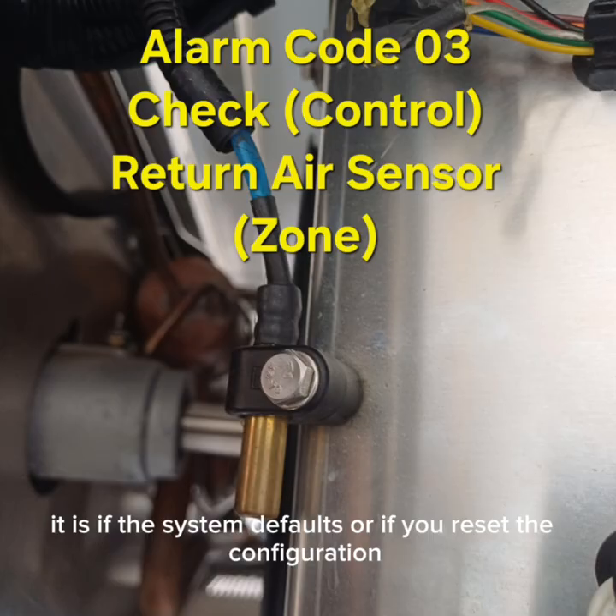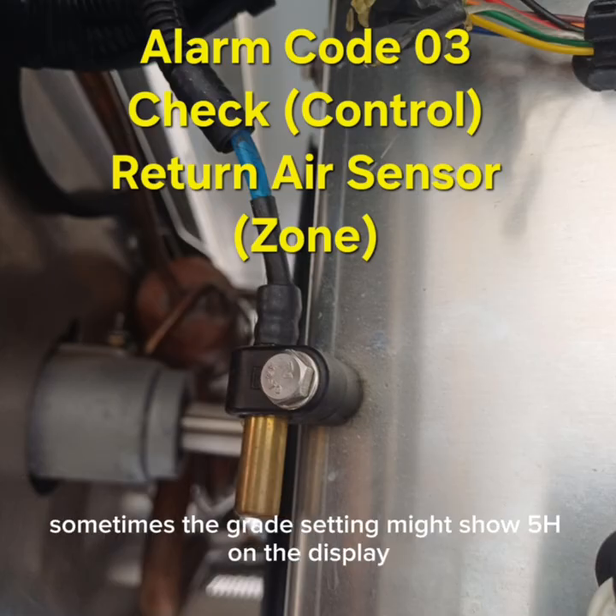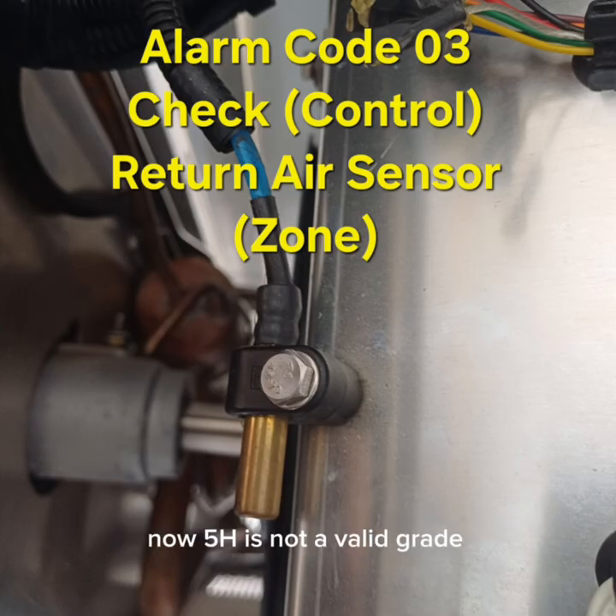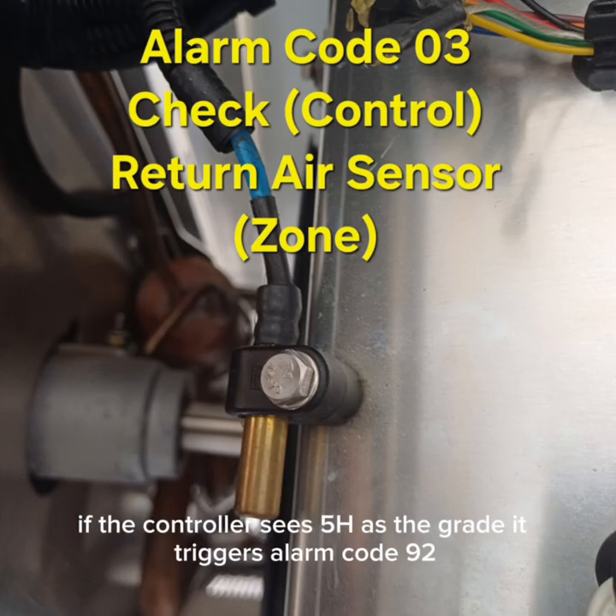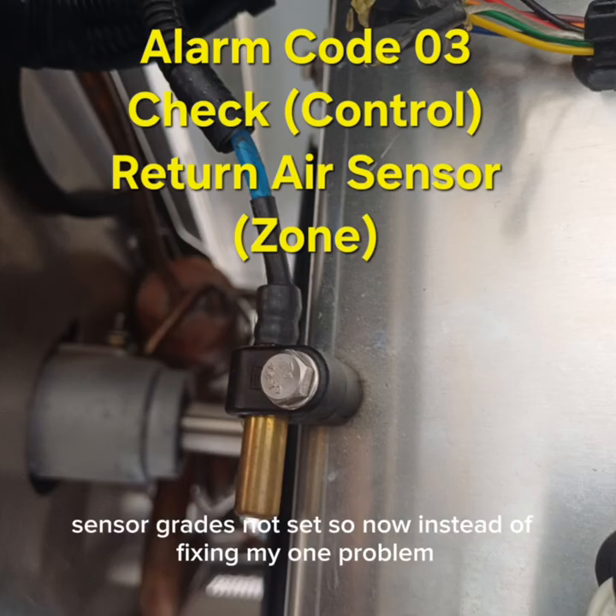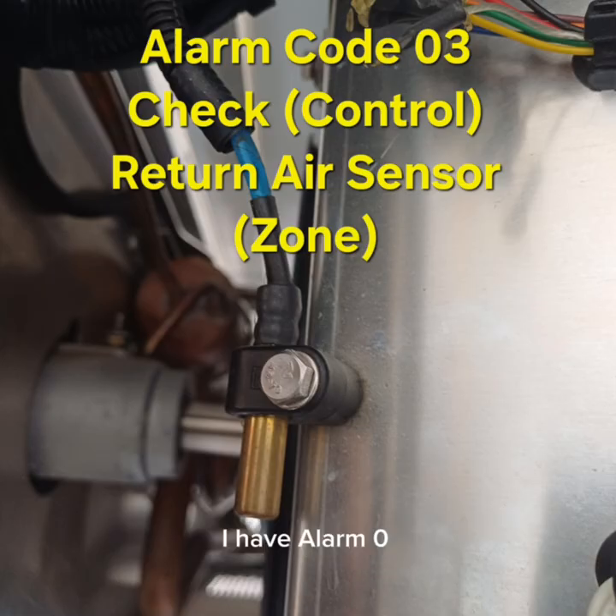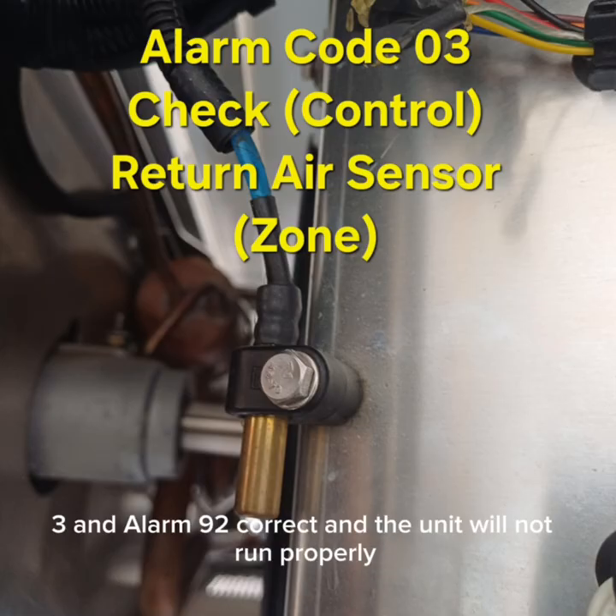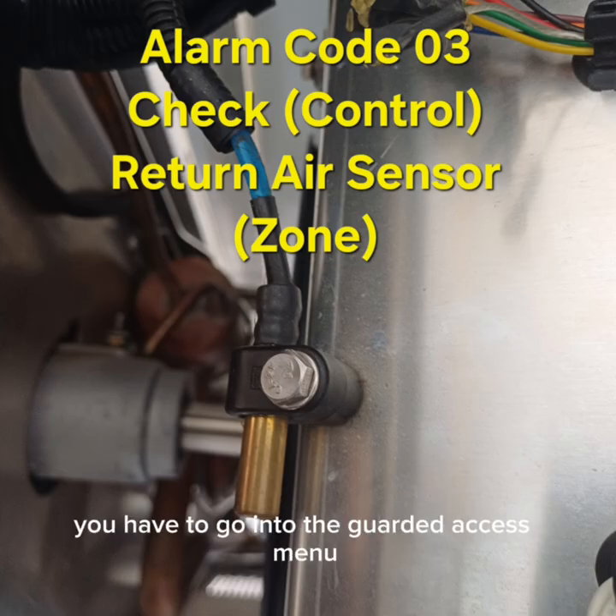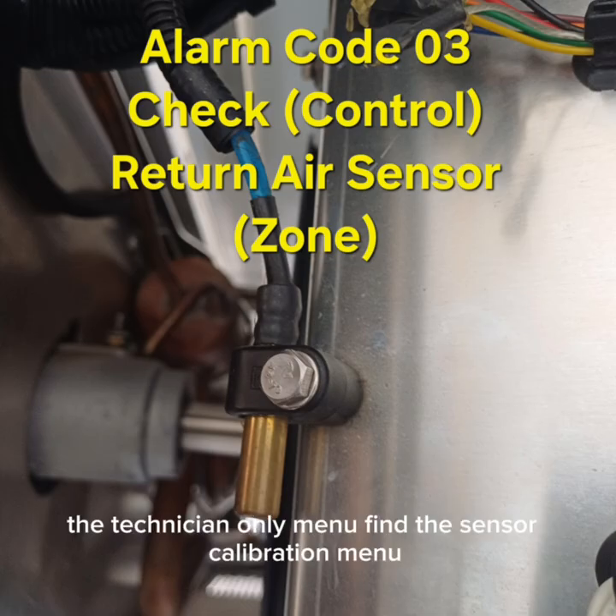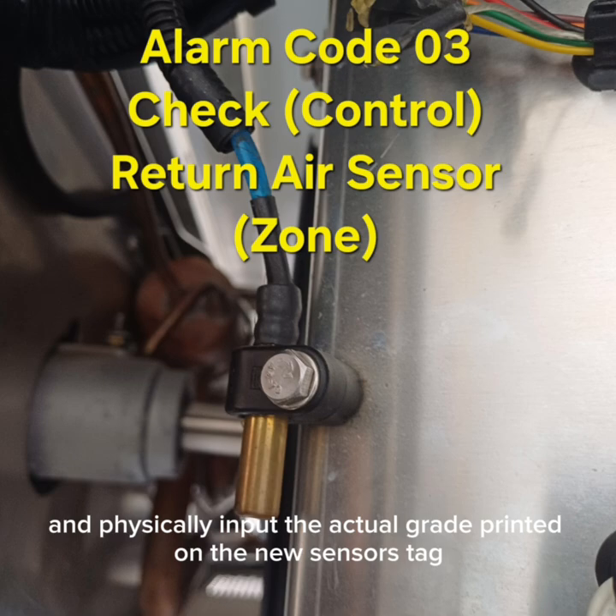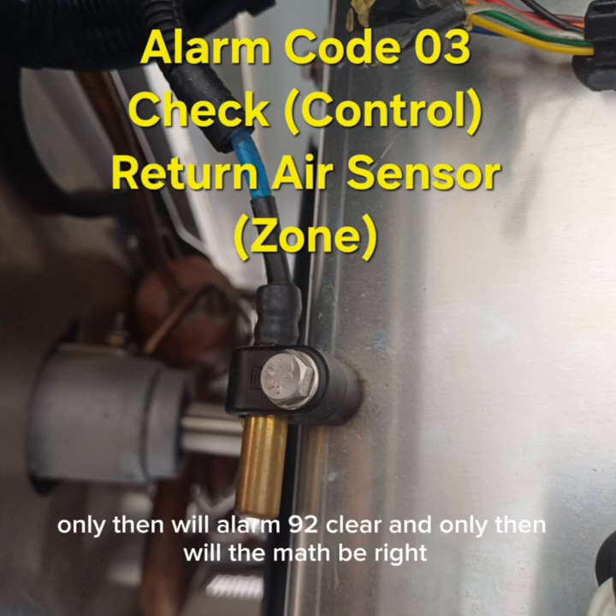It is. If the system defaults or if you reset the configuration, sometimes the grade setting might show 5H on the display. Now, 5H is not a valid grade. It's a placeholder. Okay. If the controller sees 5H as the grade, it triggers alarm code 92. Sensor grade's not set. So now, instead of fixing my one problem, I have alarm 03 and alarm 92. Correct. And the unit will not run properly. You have to go into the guarded access menu, the technician-only menu, find the sensor calibration menu, and physically input the actual grade printed on the new sensor's tag. Only then will alarm 92 clear, and only then will the math be right.